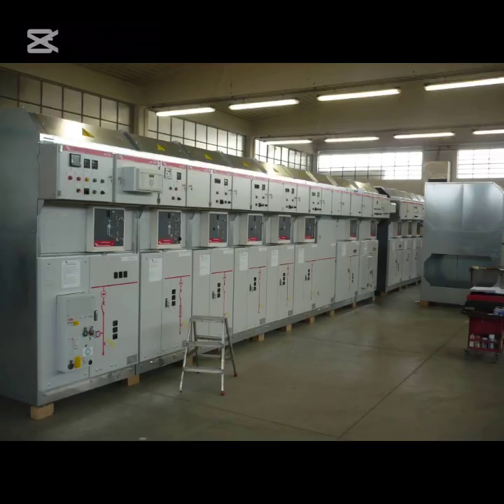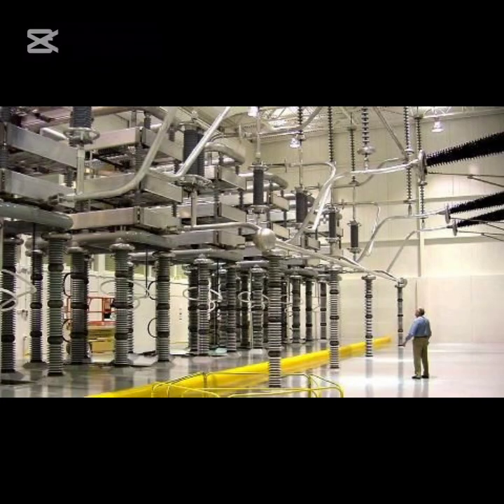For indoor type, for voltage levels below 66 kV, switchgear is usually installed indoors as it is more cost-effective. Indoor switchgear is usually of the metal-clad variety, where all live components are fully enclosed within a grounded metal enclosure.